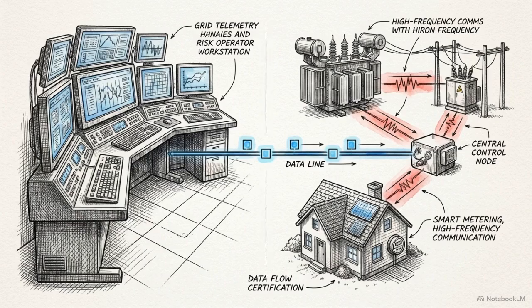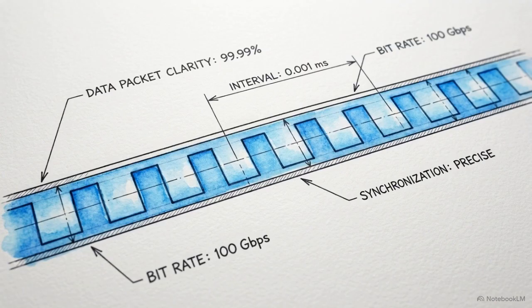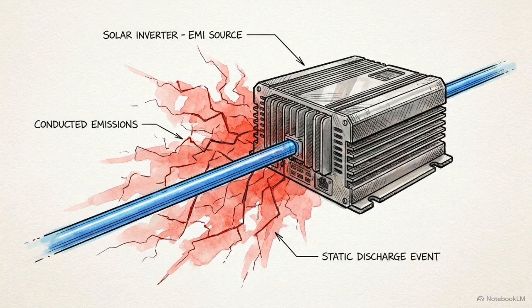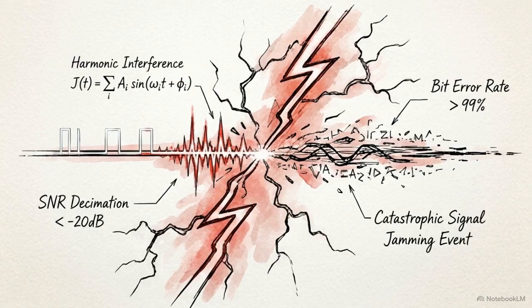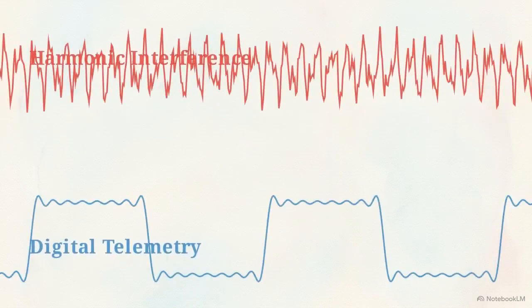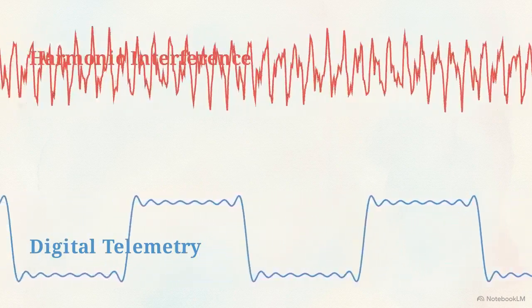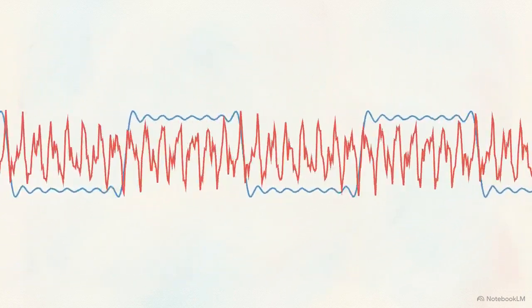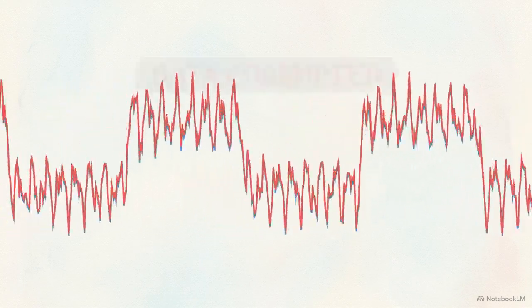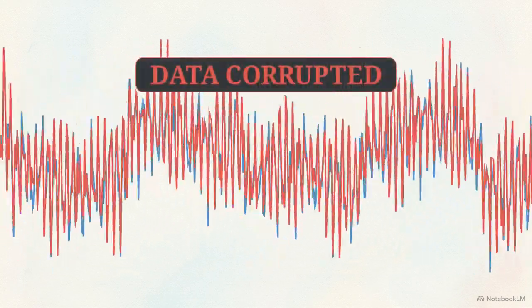Operators transmit high-frequency data signals across power lines to communicate with smart meters, substations, and automated control nodes. Those dedicated communication channels require absolute clarity. When harmonic noise from scattered inverters and variable speed drives spills into the grid, it often bleeds into those exact same dedicated frequencies. These chaotic harmonic signals physically overlap with the network's telemetry. They crash into the data signals, scrambling them until the information becomes unreadable.